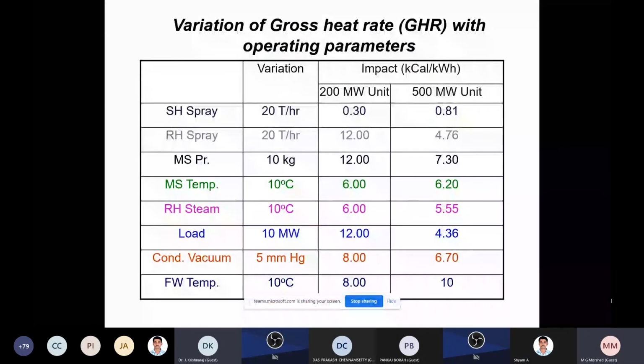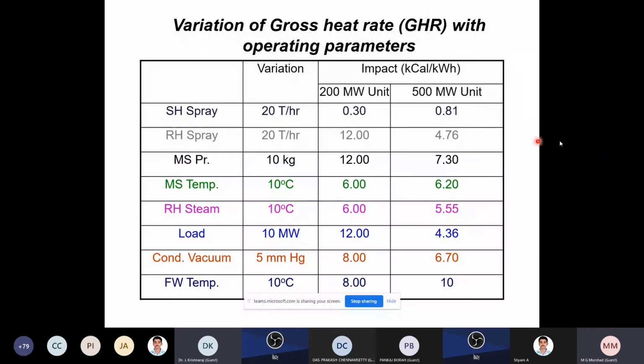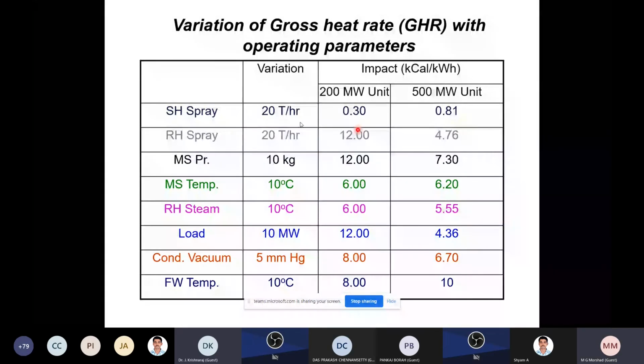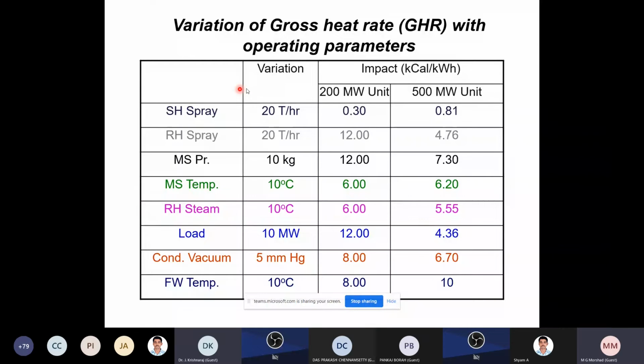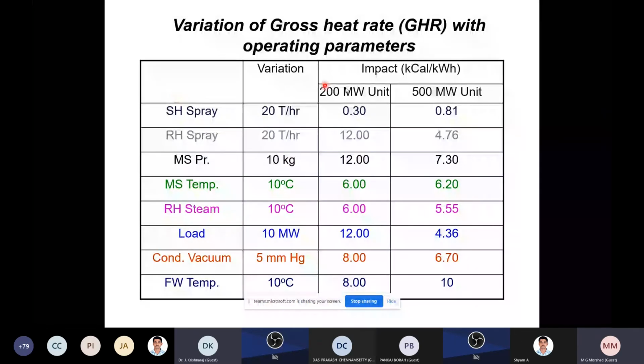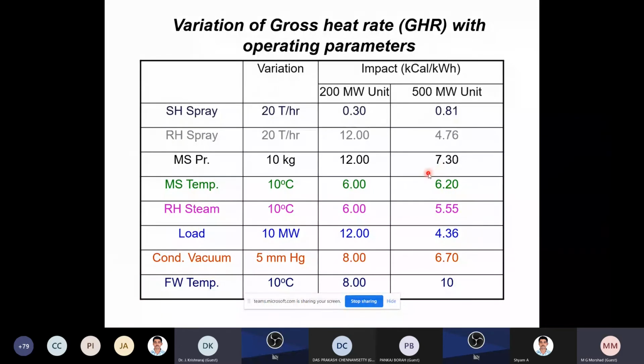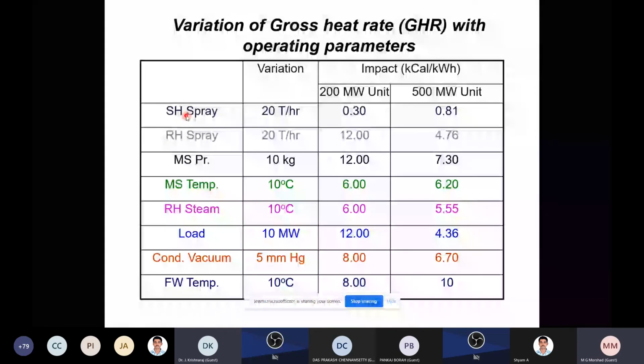Now, there are some established facts, actually published by the BEE, on the deviation or impact on gross heat rate. Suppose a superheater spray variation of 20 tons per hour: the gross heat rate deviation will be 0.3, 0.8. Similarly for reheater spray, MS pressure, MS temperature, reheater, all of the established data. So before doing all these things, you have to verify these established things in the energy audit reports themselves. Then it will be easy to trace out where the deviation has taken place. So this is a very important factor.